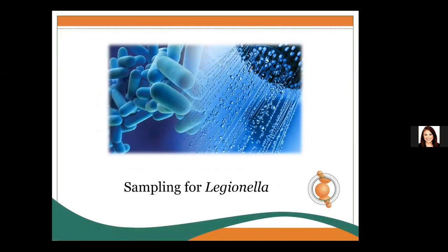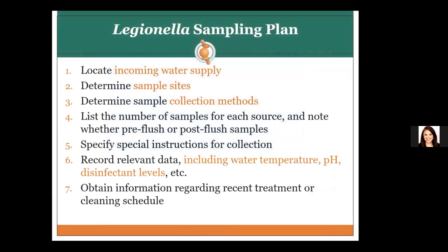For the next section on sampling for Legionella, I'll hand it over to my colleague Thomas. Hello, everyone. I'm Thomas, and we'll start to go over the sampling plans for Legionella testing. First, you'd want to locate your incoming water supply — whichever water might be entering the building — and determine the sampling sites at the facility you wish to test. Then determine the collection method, list the number of samples for each source, note whether it is pre-flush or post-flush, specify any special instructions, and record all relevant data including water temperature, pH, and disinfectant levels. Also obtain information regarding recent treatment and cleaning schedule.